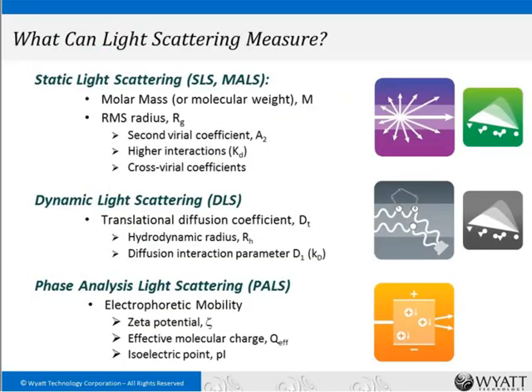So what can light scattering measure? There are various types. The first is static light scattering, also known as multi-angle light scattering, or MALS. MALS has the property that it can determine molecular weight from first principles, which is really important in that you don't have to know ahead of time what you're looking for — you don't have to calibrate columns. It also gives you the radius of gyration, or root-mean-square radius, as long as that dimension is larger than about 10 nanometers.